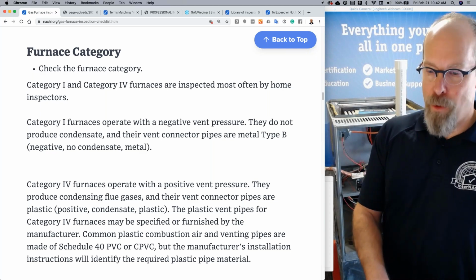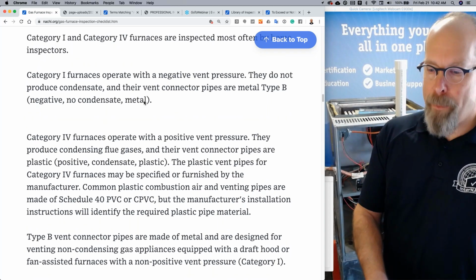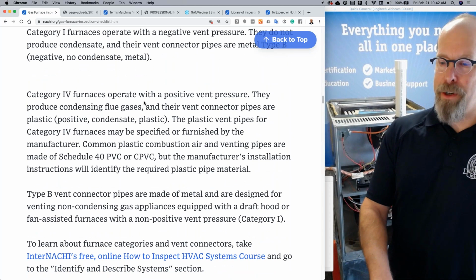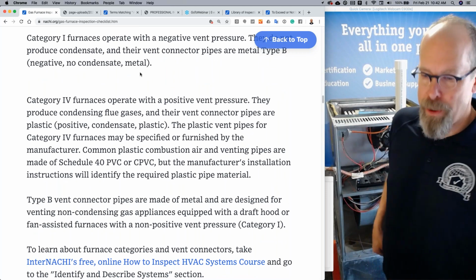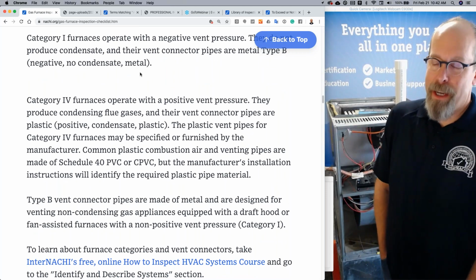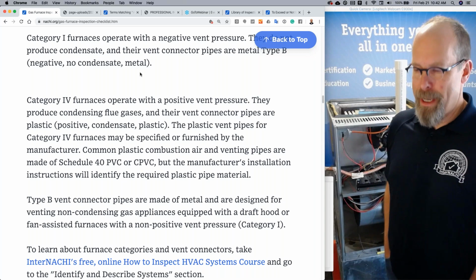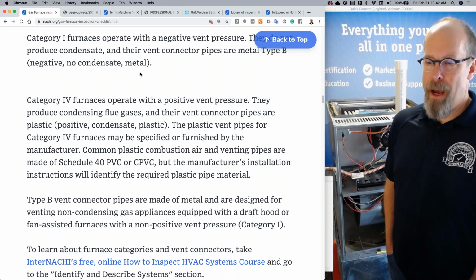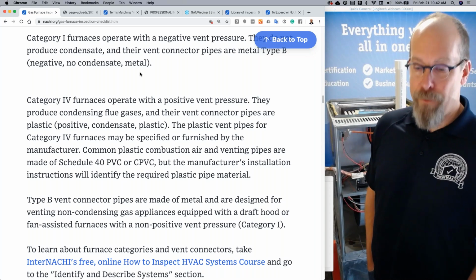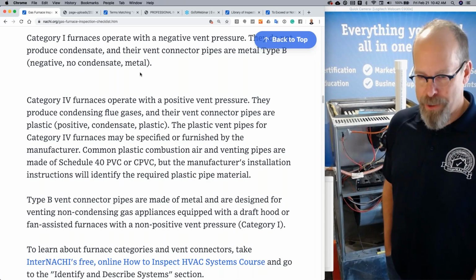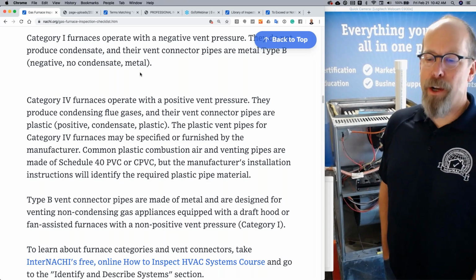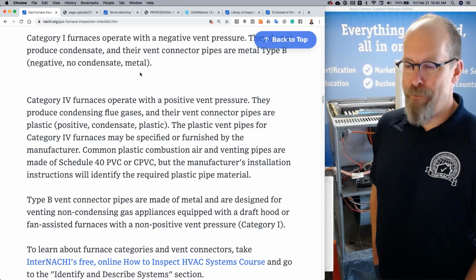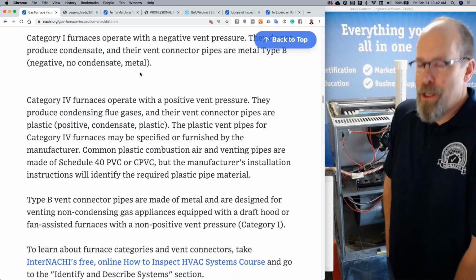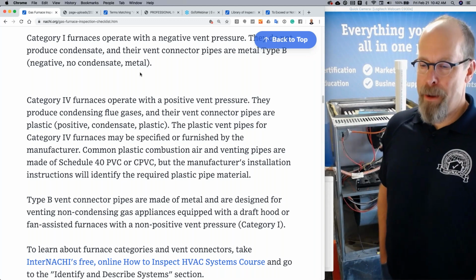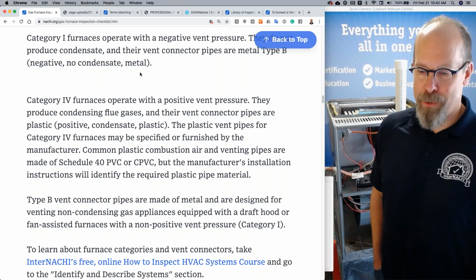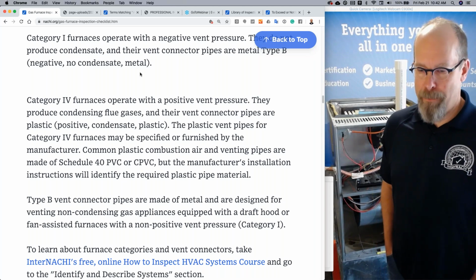Okay. Category 4 furnaces operate with a positive vent pressure, and they produce condensing flue gases, and their vent connector pipes are plastic, positive, condensate, plastic. And the plastic vent pipes for category 4 furnaces may be specified or furnished by the manufacturer. The common plastic combustion air and venting pipes are usually Schedule 40 PVC or CPVC, but the manufacturer's installation instructions will identify the required plastic pipe material.